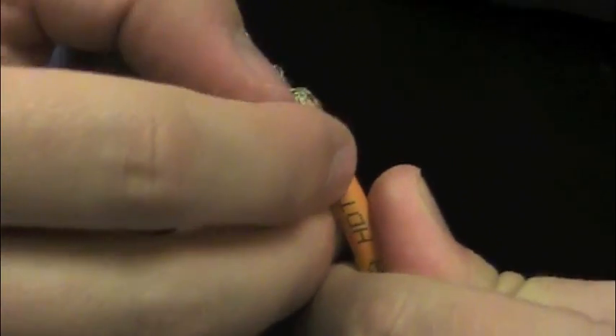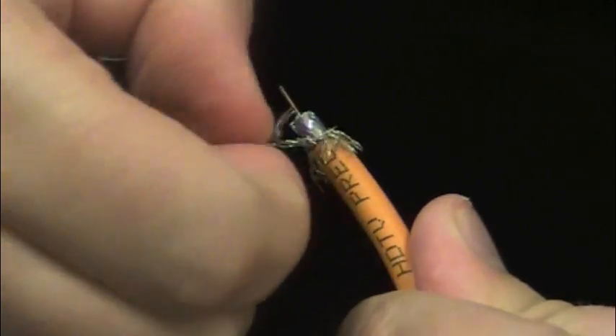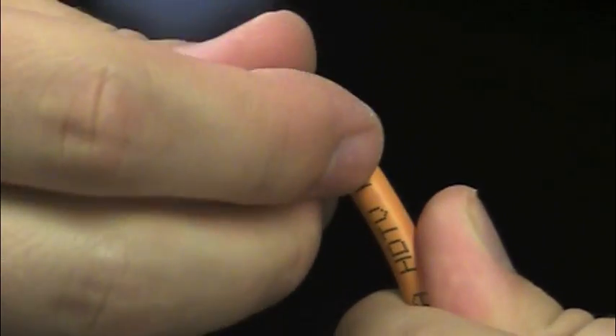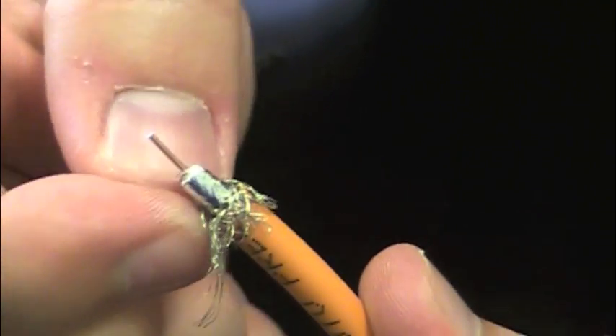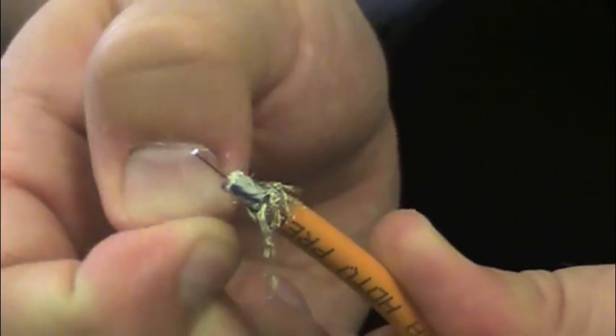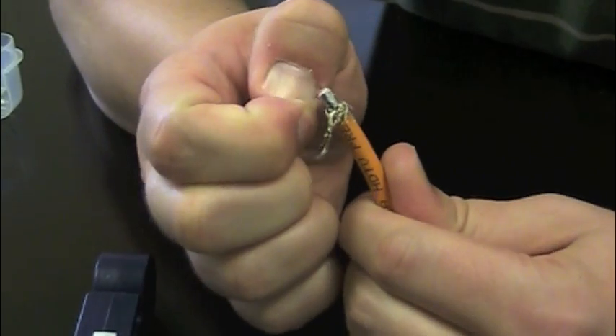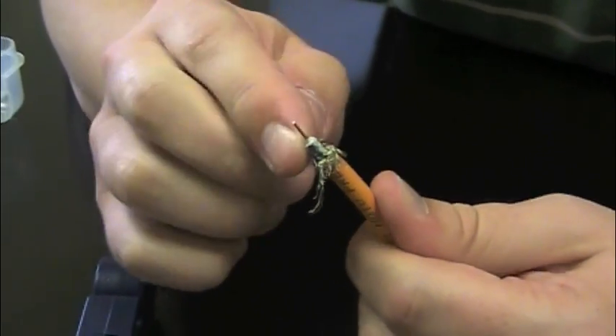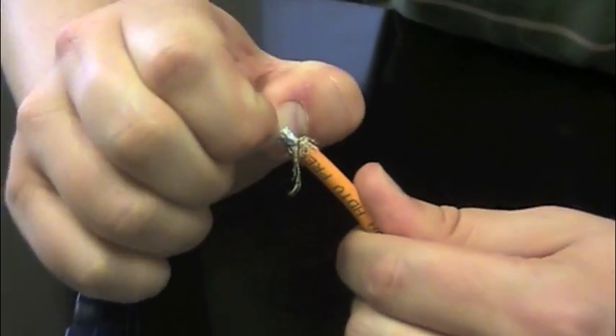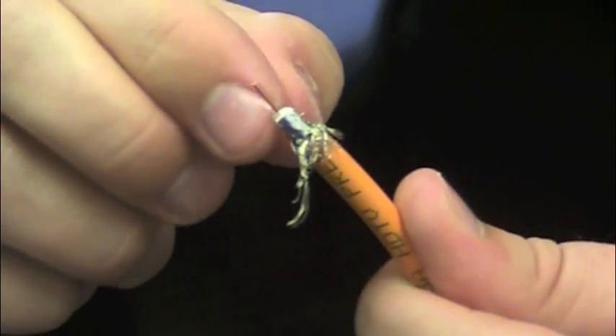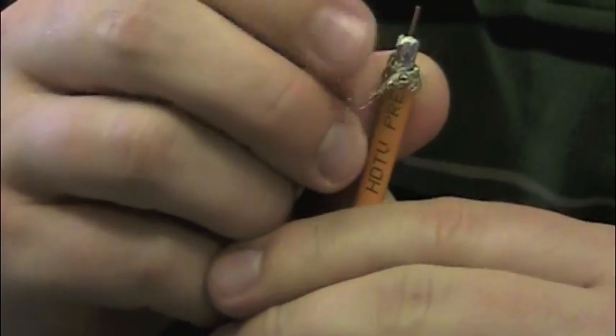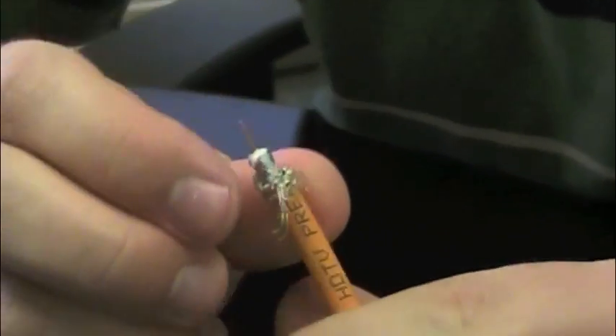You might lose some strands of braid. It's okay to lose some, but you don't want to lose a whole bunch. And as I said, as you're pulling this off, you're going to make sure that the center conductor is free from any strands of braid, because again, that will short it. So in this case, I'm trying to pull the center conductor, make sure it's clean. And you just do a little physical examination. Make sure that there's nothing shorting. We're good.